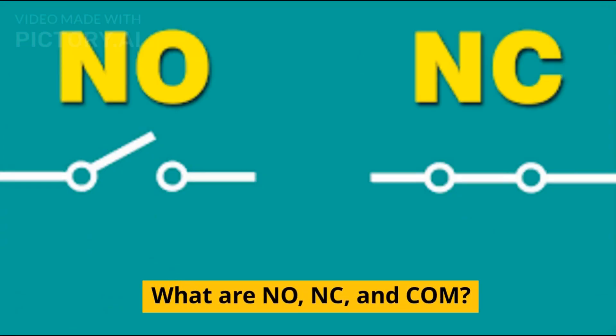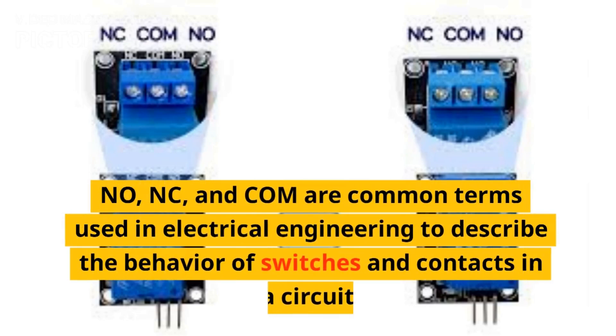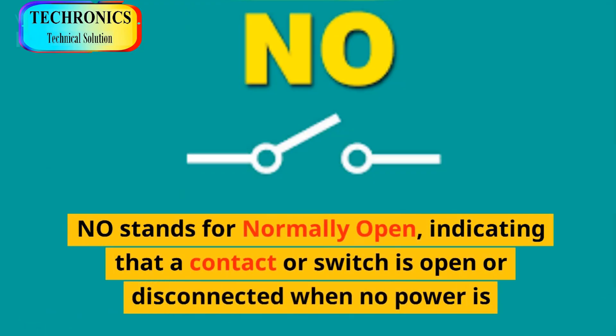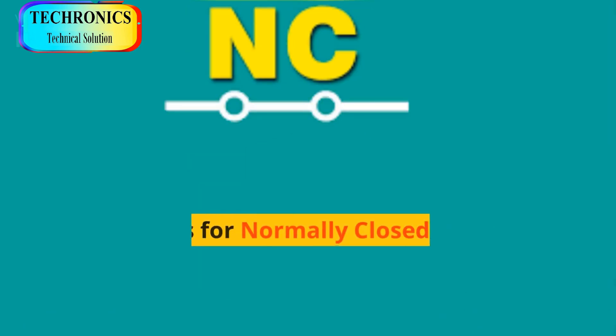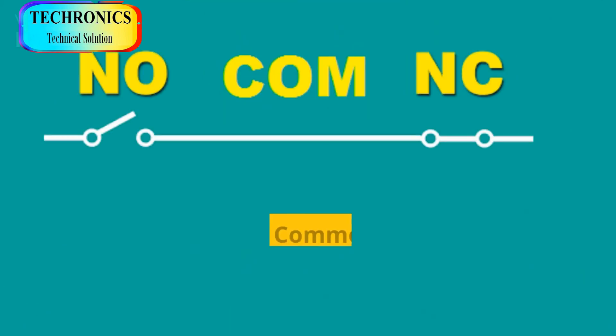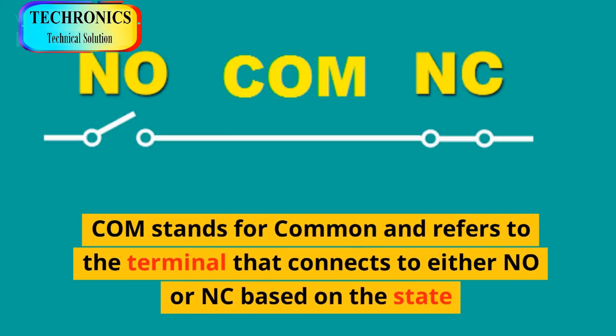NO, NC, and COM are common terms used in electrical engineering to describe the behavior of switches and contacts in a circuit. NO stands for normally open, indicating that a contact or switch is open or disconnected when no power is applied. NC stands for normally closed, meaning a contact or switch is closed or connected when no power is applied. COM stands for common and refers to the terminal that connects to either NO or NC based on the state of the switch.